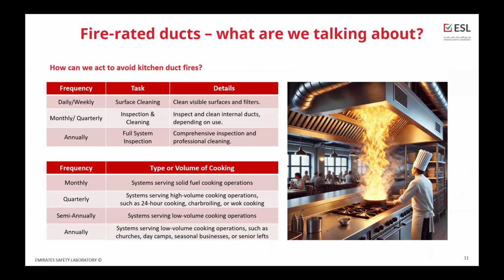By frequent cleaning, frequent inspection, and good maintenance of these systems. Having a fire-rated duct doesn't mean that you don't need to maintain the duct or the extraction system. You can see here the two tables. One is the European approach and the other is the NFPA guidelines. Both of them are based on frequent maintenance, inspection and cleaning, depending on the task or the volume of the kitchen. So this is something which cannot be avoided, which cannot be missed. It has to be done manually, either monthly, quarterly, or even, in some guidelines, as a daily task.